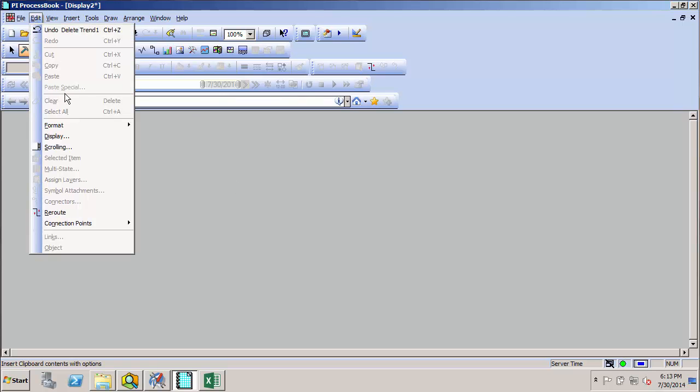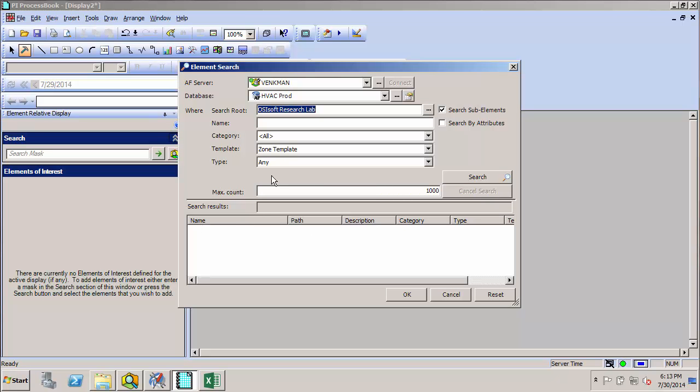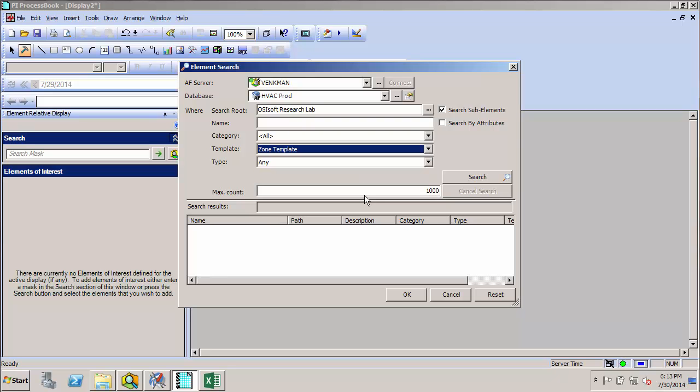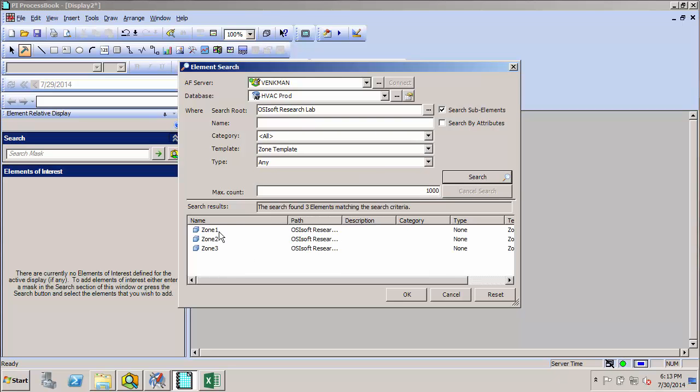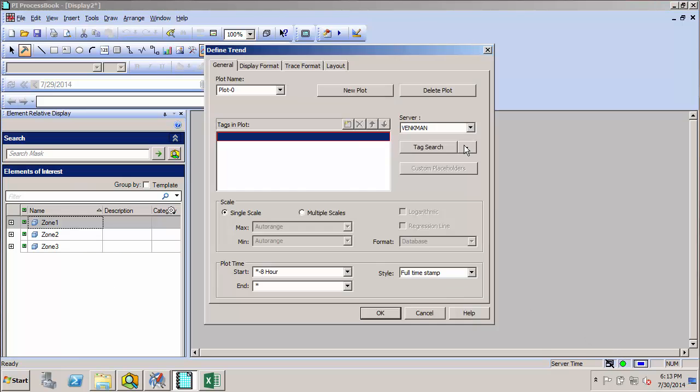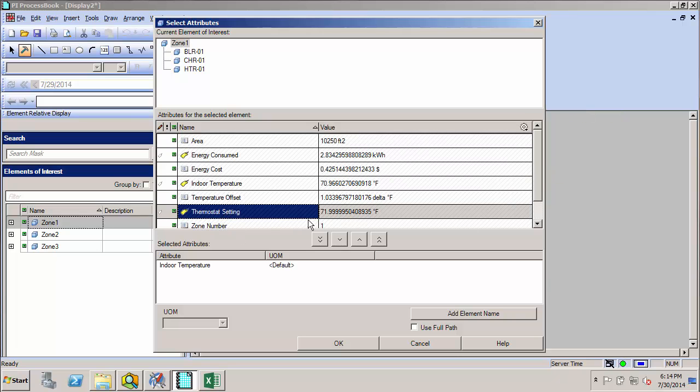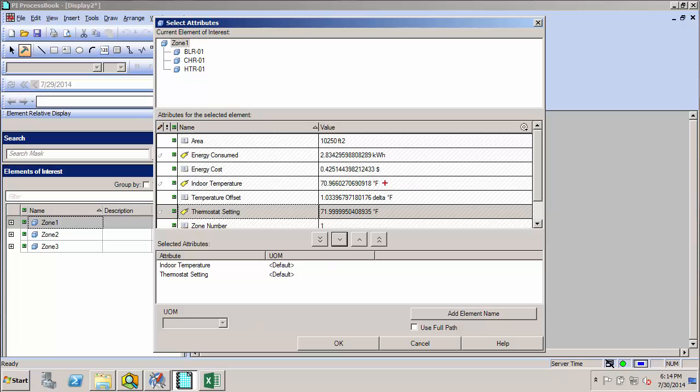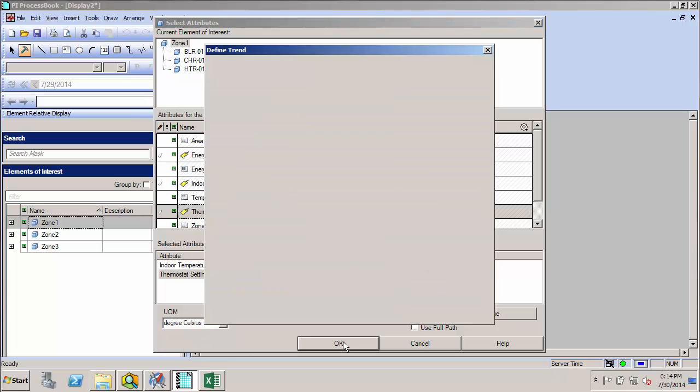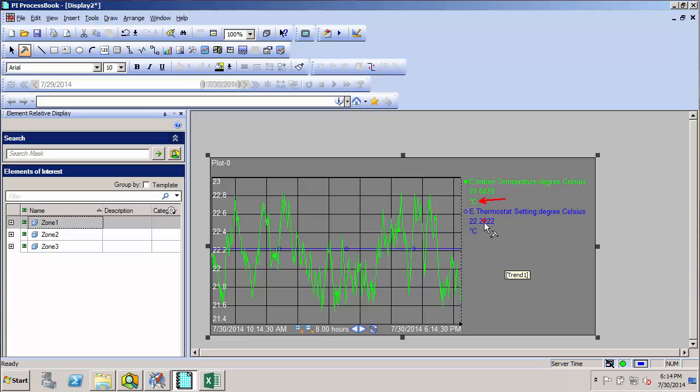Here, with the AF integration, I can just create an element-relative display. And here's another nice feature of AF. It does automatic unit conversions. So even though my two temperatures here are in degree F in the database, on the client side I can choose any temperature I want. So let's go with Celsius here. Click OK, OK, and now I immediately have a trend of my indoor temperature and thermostat setting. And you can see that they're using degrees C.